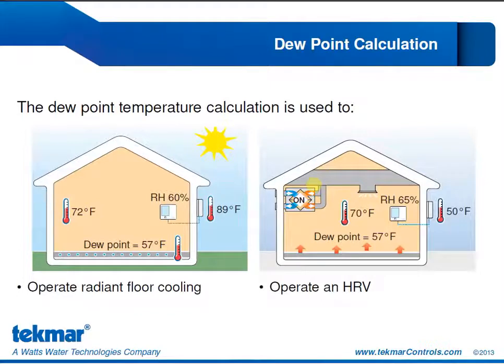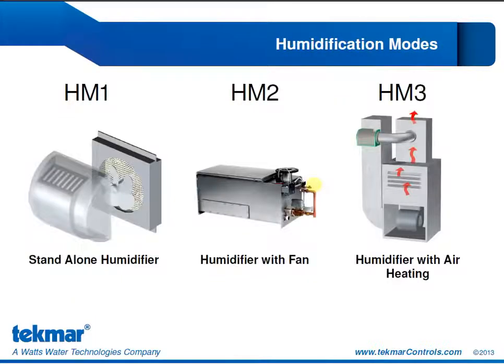To operate an HRV, the 557 does the dew point calculation. And we're only going to operate that HRV if the outdoor temperature is at least 5 degrees below the indoor dew point. We're going to discuss that in greater detail when we go over the dehumidification modes of the 557.